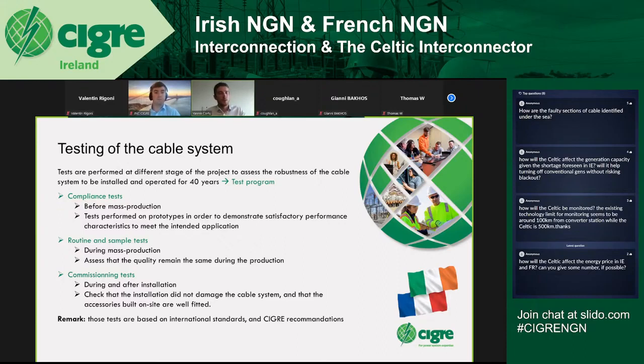During the mass production, we will perform routine and sample tests to assess that the quality remains the same during the whole production. This production will be more or less 2 years or 2.5 years. This is done in factories before the installation part. During the installation and after it as well, we will have the commissioning test that will be performed to check that the installation did not damage the cable system and that the accessories that are built on site are well fitted. And after that, once everything is checked, we can take over the cable link. Obviously, those tests are based on international standards and CIGRE recommendations.